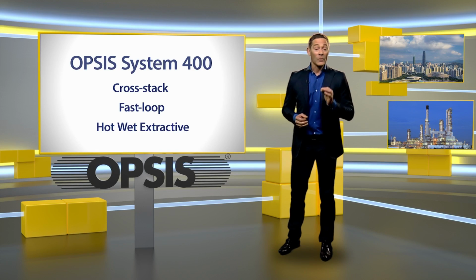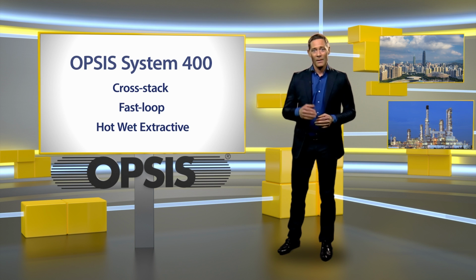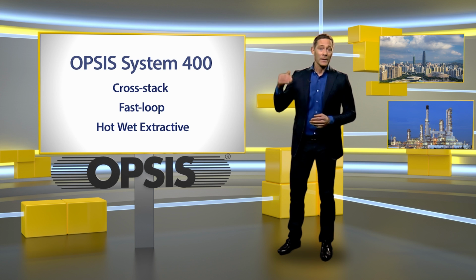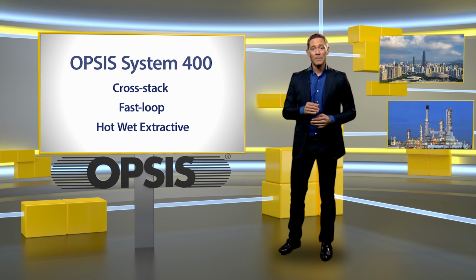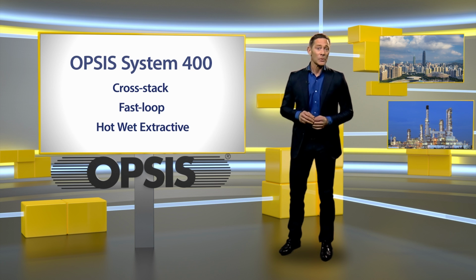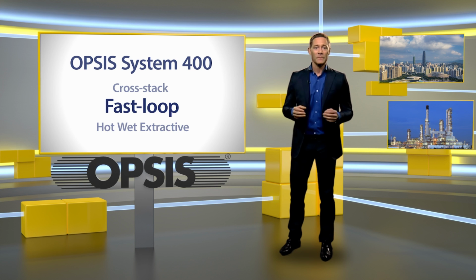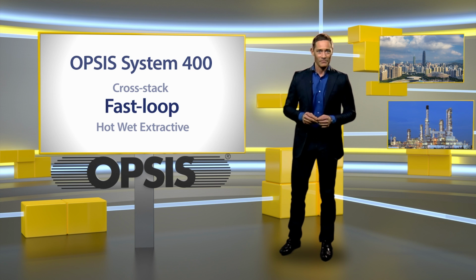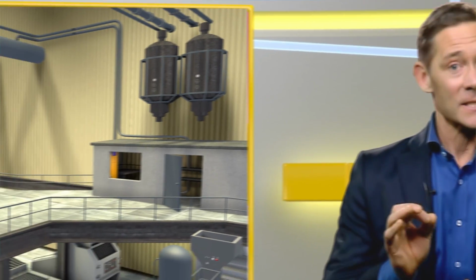However, there are some plants where the measurement point can be difficult to access. For example, it could be located high above floor level, or there might be a long distance between the measurement point and the analyzer, making it difficult to find somewhere suitable to position the transmitter and receiver. But there is a solution for this: the OPSIS System 400 Fast Loop. Here, at this power plant, the measurement point is difficult to access.